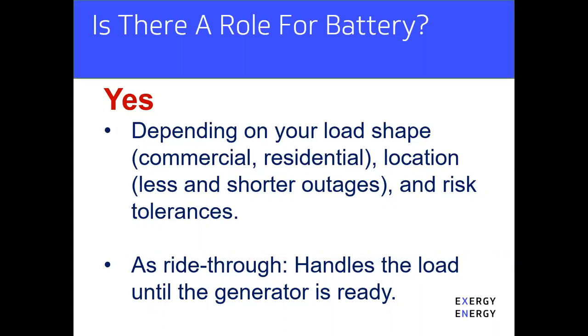But the greatest use of a battery is what we refer to as ride-through, which handles the load until the generator is ready. Think of it this way: for many organizations, if the power goes out and comes back on in a minute or two, nobody really cares. Maybe it's a grocery store, the freezer goes down for a minute, nothing bad happens, and if it comes back fairly quickly, no harm no foul. But in some instances that's not true, and you really need to be able to ride through the load.